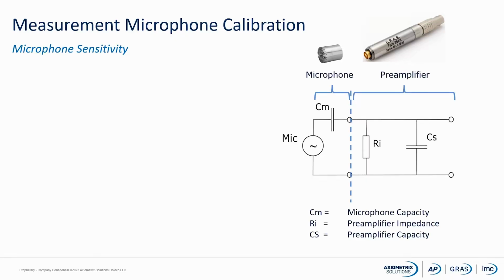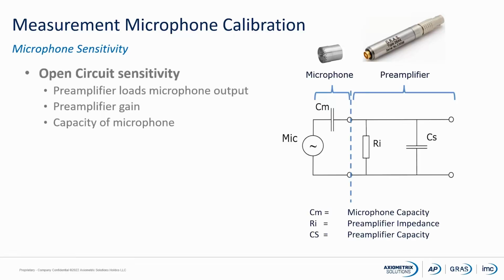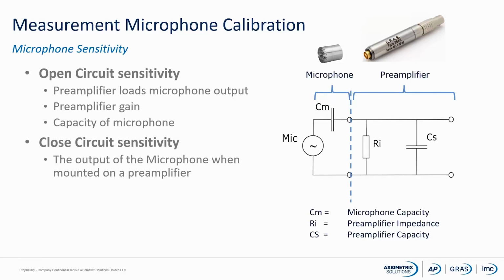Let's see what we actually are doing when we are making microphone calibrations. When we are looking at the microphone sensitivity, then in the standard it is described only for the microphone capsule. The microphone capsule is only this one here. And it is described as an open circuit sensitivity. It means that's the sensitivity for the microphone capsule without the load from a preamplifier. So we are not looking at the preamplifier gain, we are only looking at the microphone. Closed circuit sensitivity is the sensitivity we will measure on the output of the preamplifier. So it is the sensitivity for both the microphone and the preamplifier.